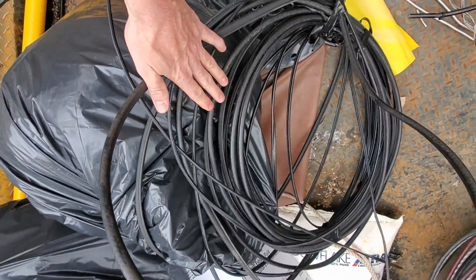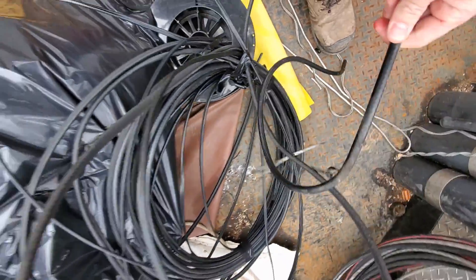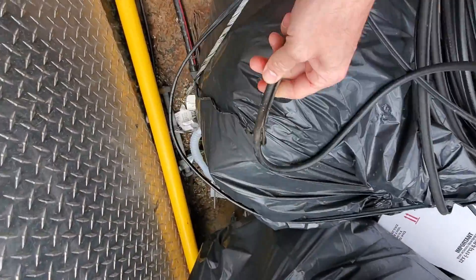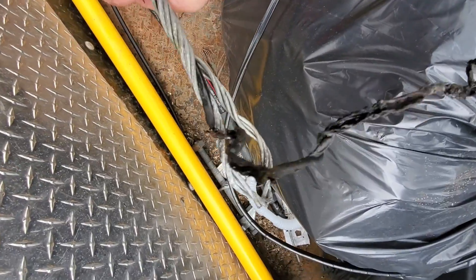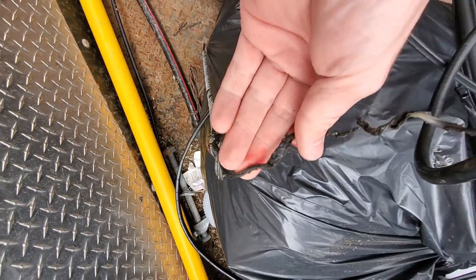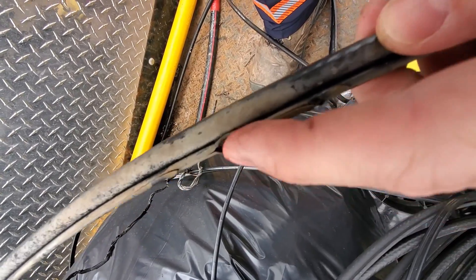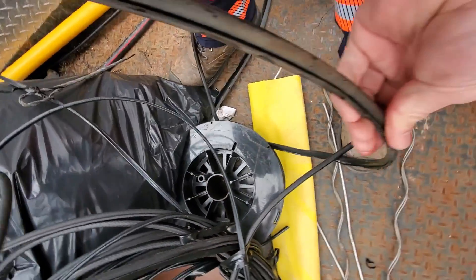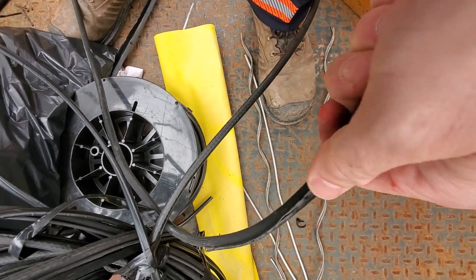So the office is by the dumpster here, the truck is full of junk, and I just cut this off the pole. This is a coax cable and you can see the jacket on the cable is completely melted. There was actually 7200 volts that went right through it — the steel is completely disintegrated except for that one piece. There was steel inside here, and as we can see, the steel carrier for the coax — the steel is completely disintegrated in multiple points as that 7200 volts traveled through this entire cable from a pole that was across the street.